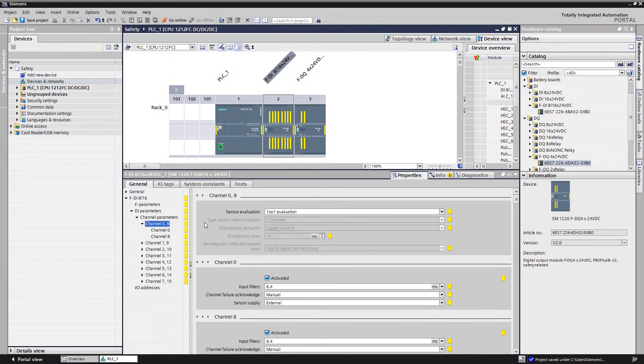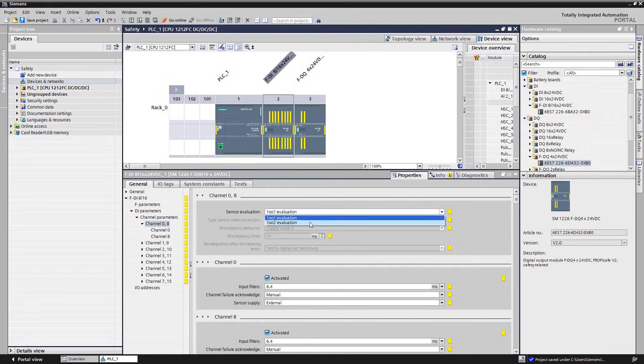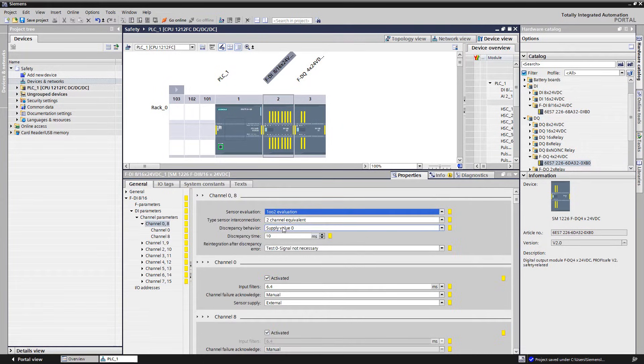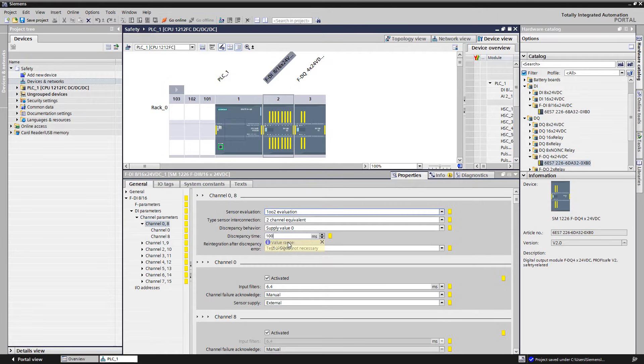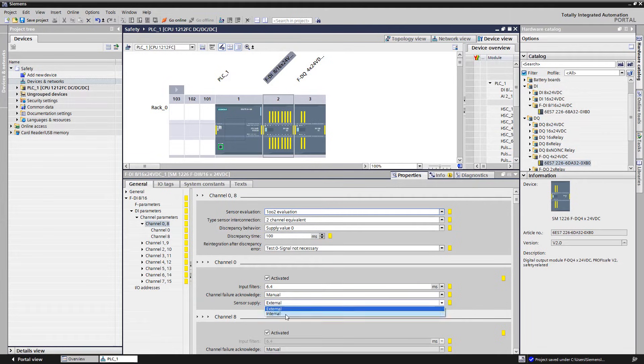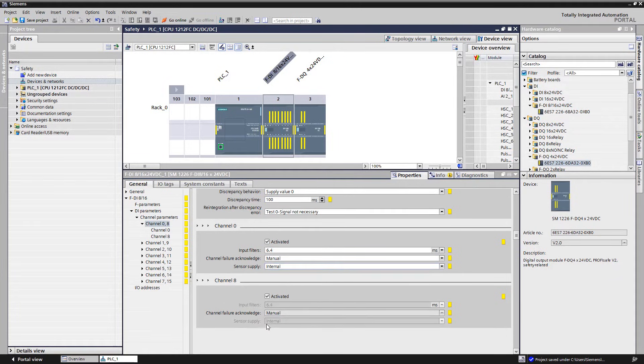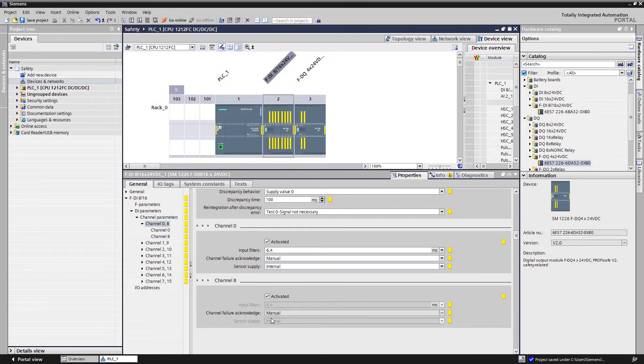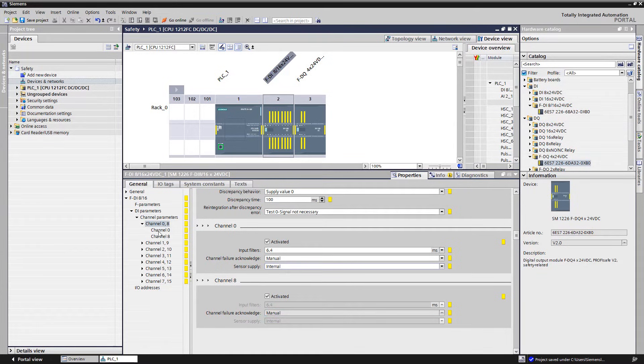For the evaluation of the emergency stop, we select a two channel evaluation 1 out of 2 with a discrepancy time of 100 milliseconds and use the internal encoder supply. Since we already selected 1 out of 2 above, the second channel is automatically assigned with the same settings.